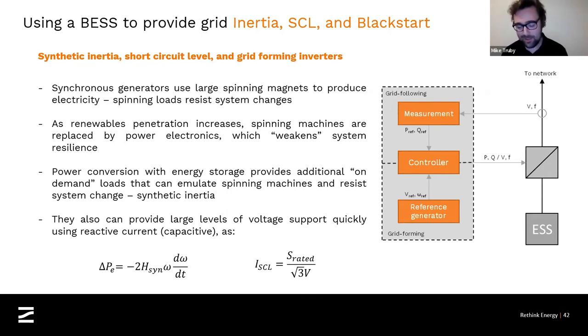But basically what this means for battery energy storage is that inverters, whilst they themselves have no inertia, are power electronics. They switch instantaneously, they respond instantaneously, and we can mimic what a synchronous machine is doing using an inverter with a dispatchable asset, i.e. a battery, behind it. So we can call on those batteries and say, this is the amount of power that we need to top up into the network in this profile to mimic what a synchronous machine would be doing right now to basically deaden this transient. That is something we have demonstrated through system studies, and something we will be deploying, as Simon says, in our next phase of large-scale projects.